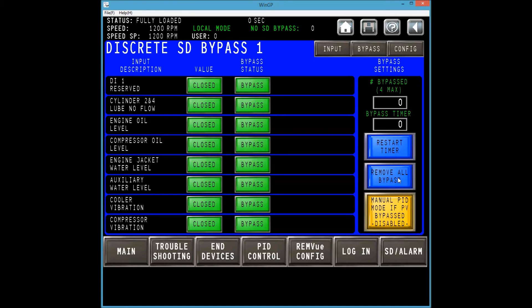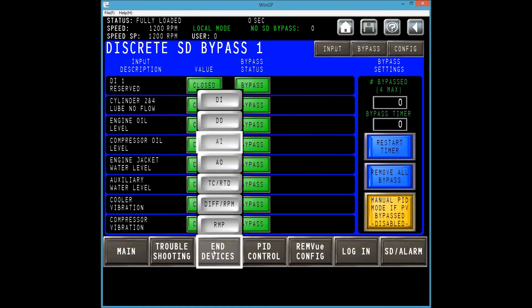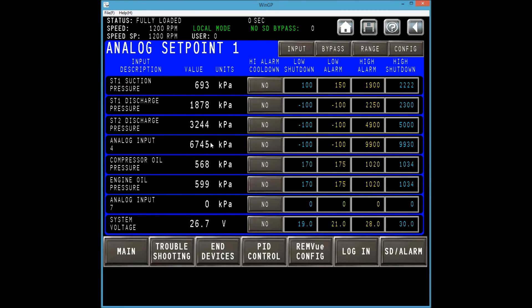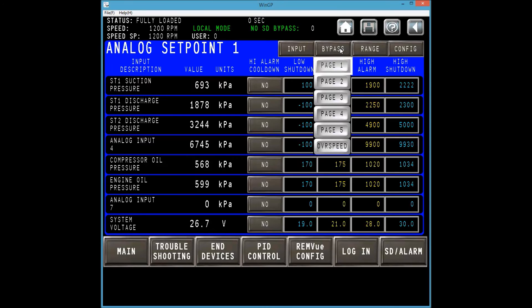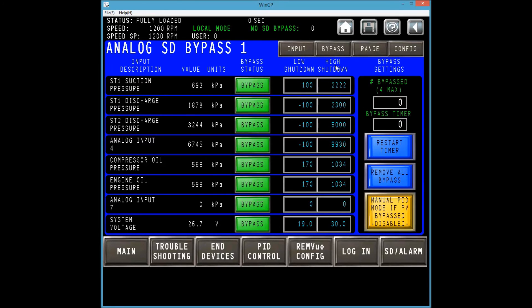If instead of bypassing a DI I.O. channel we decide to bypass an AI or TC channel, we will notice a few differences. By pressing End Devices and selecting AI for example, we will see the first screen is different. However, the bypass button on the top right is still the same. If we select page one, we will notice a slight difference, but the bypass functions on the right remain the same. You may have noticed a manual PID mode if PV bypass button on the bottom right of the bypass screen. This button allows the user to set any associated PIDs to manual mode when bypassing I.O. channels. Manual mode allows the user to make changes to the bypass I.O. channel without having affected the PID.